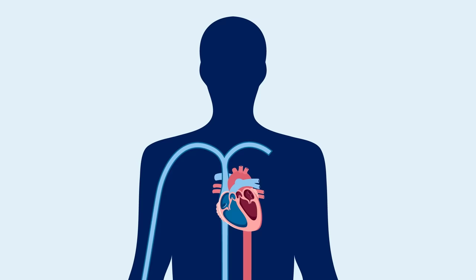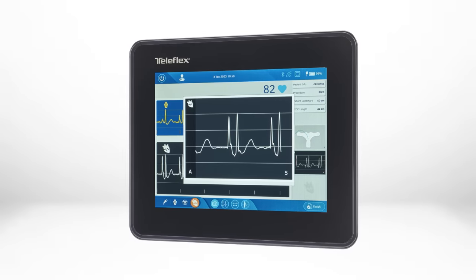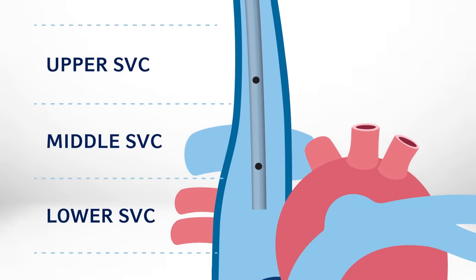The VPS Rhythm DLX device uses magnetic tracking, ECG-based tip confirmation technology, and max P-wave and negative deflection for the clinician to verify PICC placement, allowing for precise placement of the PICC in the lower one-third of the superior vena cava.